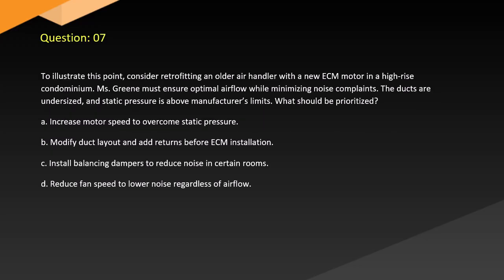Question 7. To illustrate this point, consider retrofitting an older air handler with a new ECM motor in a high-rise condominium. The engineer must ensure optimal airflow while minimizing noise complaints. The ducts are undersized and static pressure is above the manufacturer's limits. What should be prioritized? A. Increase motor speed to overcome static pressure. B. Modify duct layout and add returns before ECM installation. C. Install balancing dampers to reduce noise in certain rooms. D. Reduce fan speed to lower noise regardless of airflow.